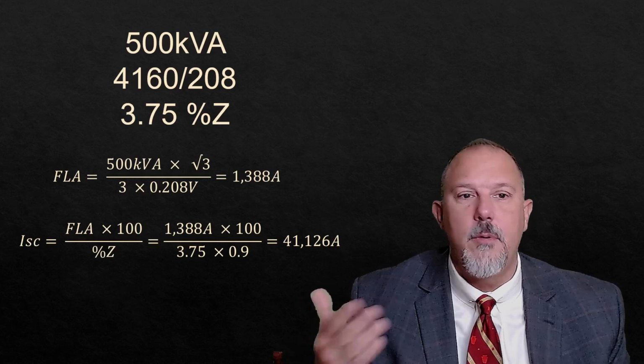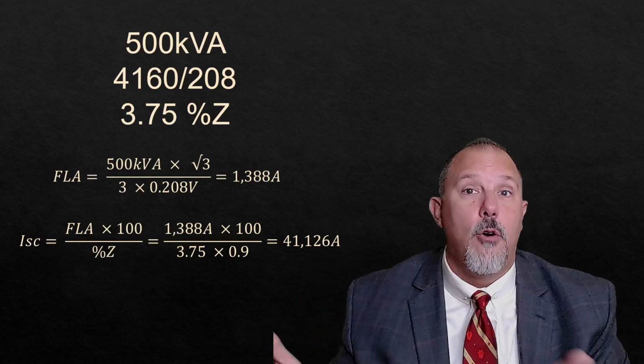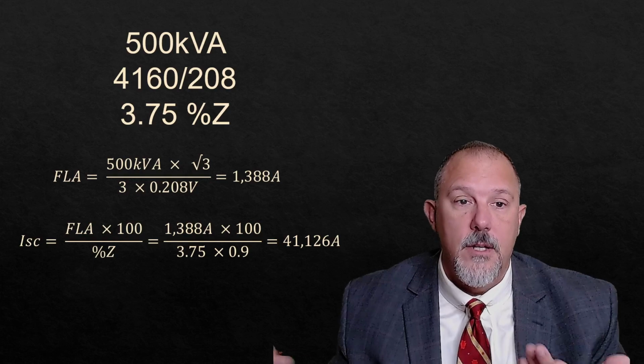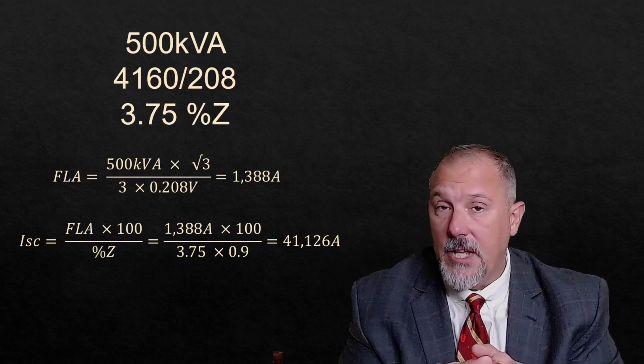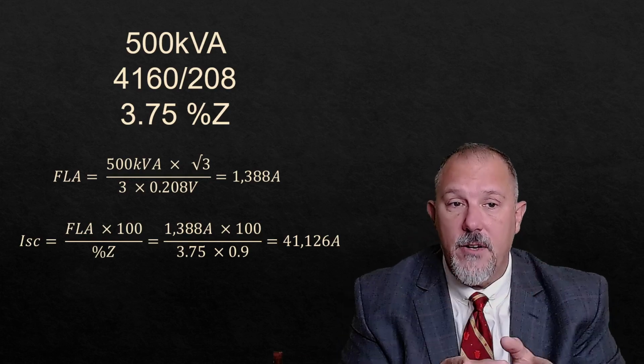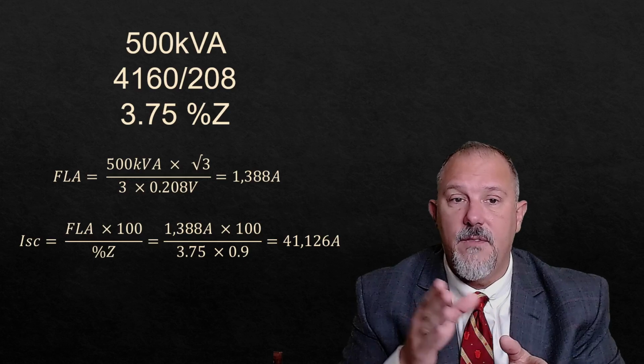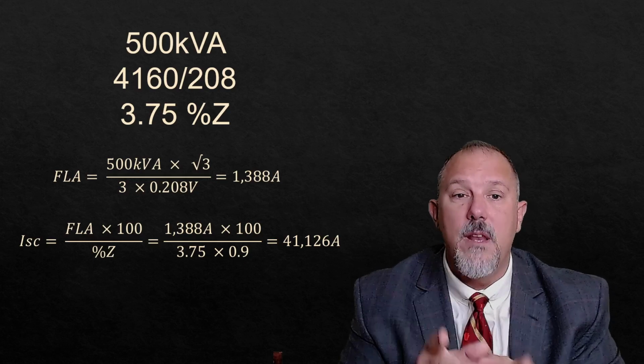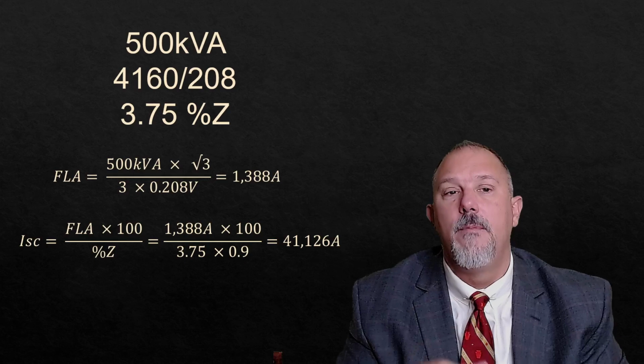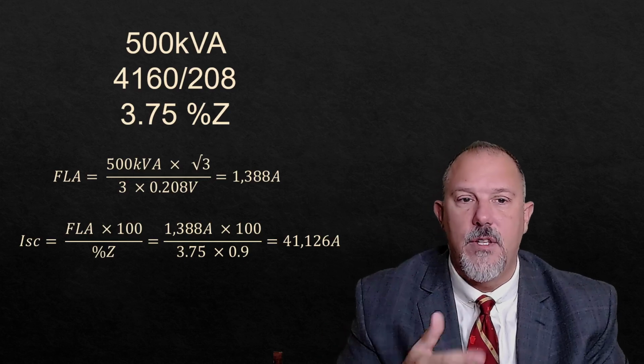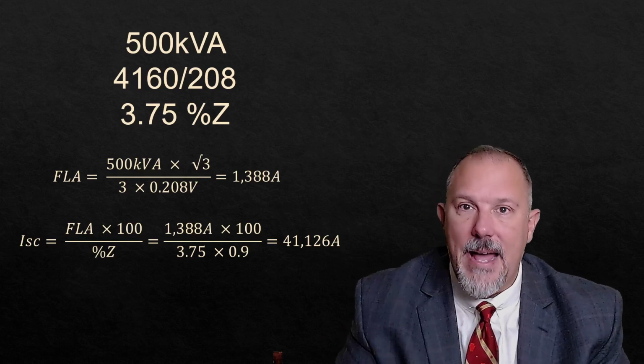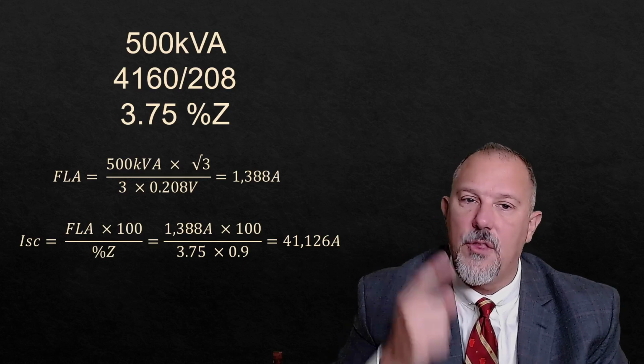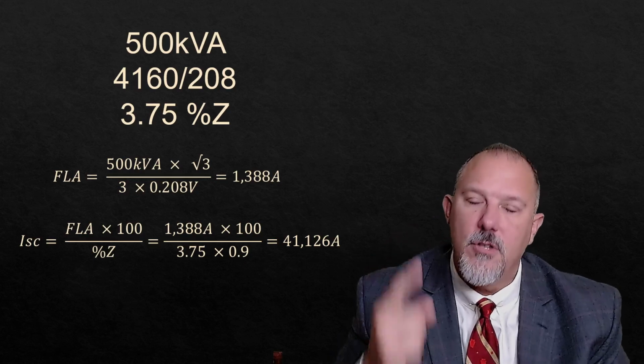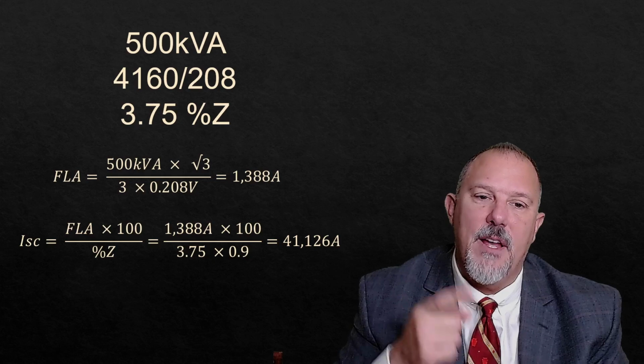Or square root of 3 divided by square root of 3 is equal to 1 over the square root of 3. And this is a three-phase application too. So 500 kVA times the square root of 3 divided by 3 divided by the 0.208 is 1,388 amps for the secondary full load amps of this transformer. To get the maximum available fault current, I just take 1388, multiply that by 100, and divide that by 3.75.